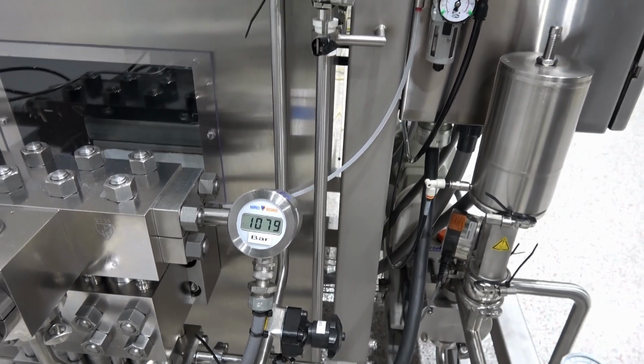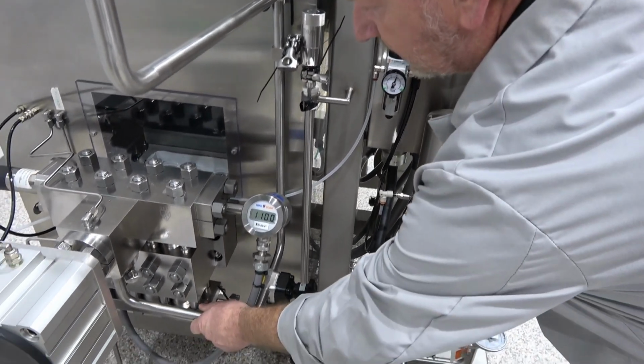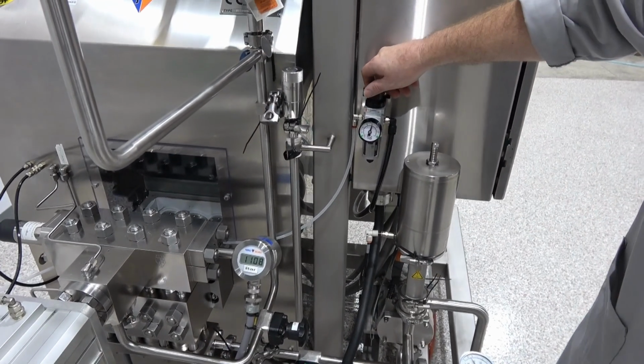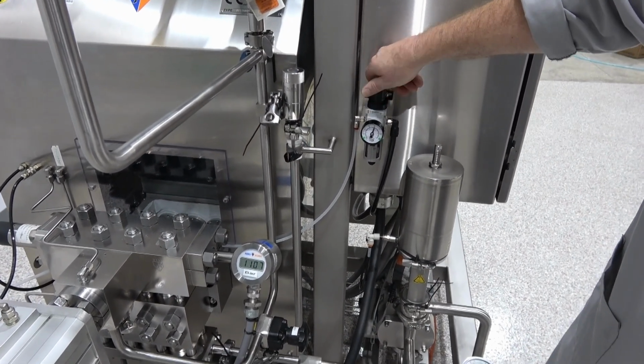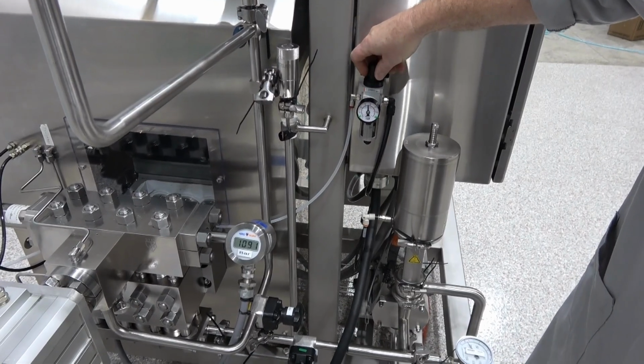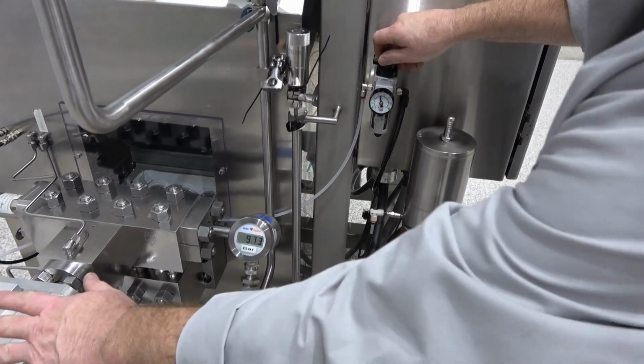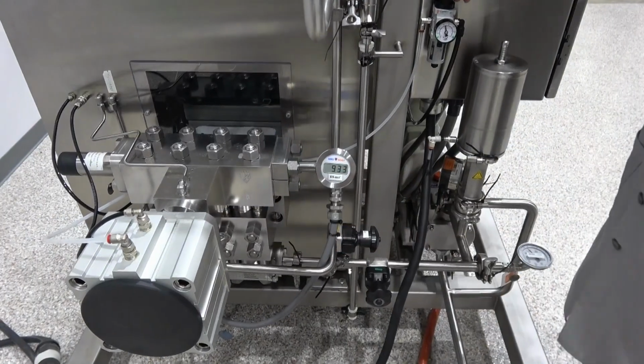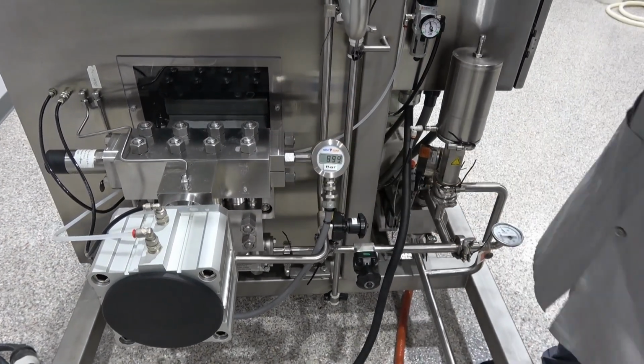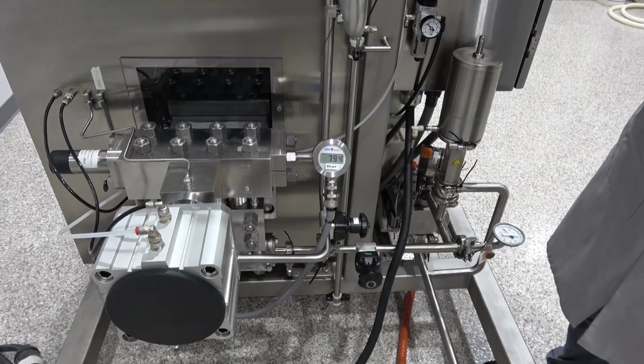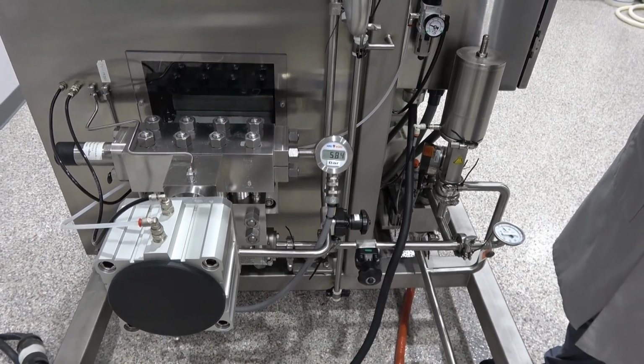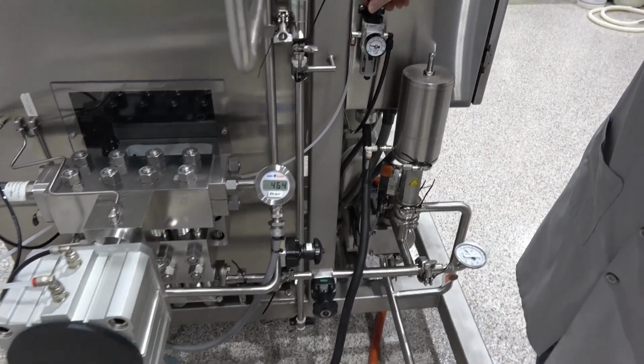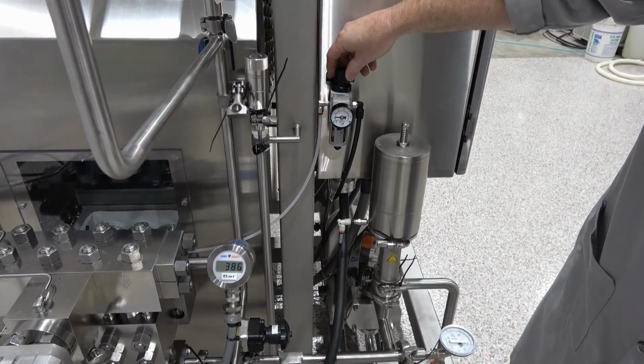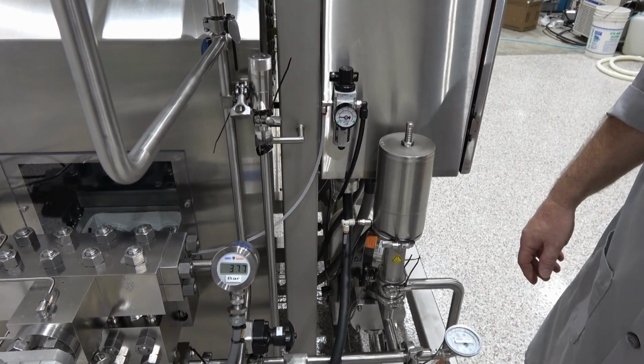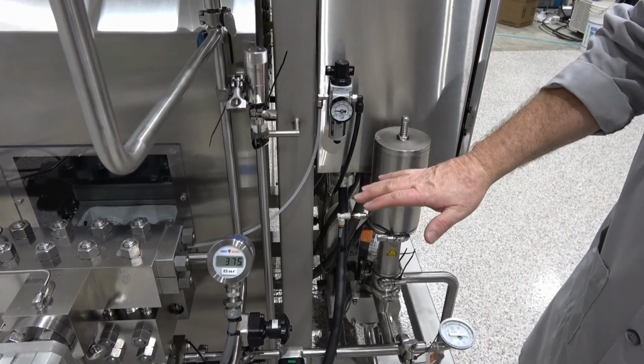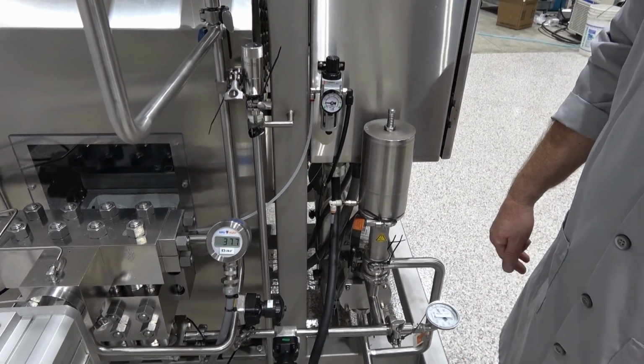So we don't want to run it too long because the heat really builds up, and we're not running a chiller right now to extract the heat. So I'm going to crank down the pressure again here, and by just lowering the air pressure, we're essentially lowering the air pressure on this diaphragm, so then it releases off the high pressure pump head. So I like the hand dial one. I can dial it in where I want it and run it. And once you set your air pressure there, it just stays really consistent. You can just see how consistent it stays there.